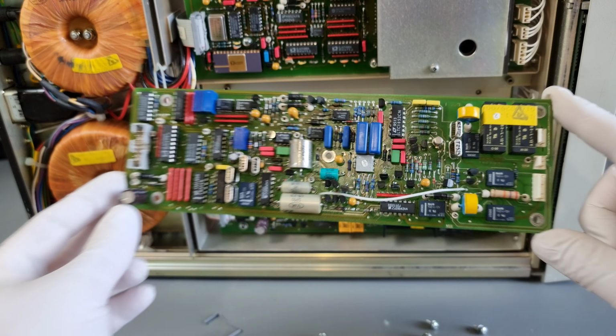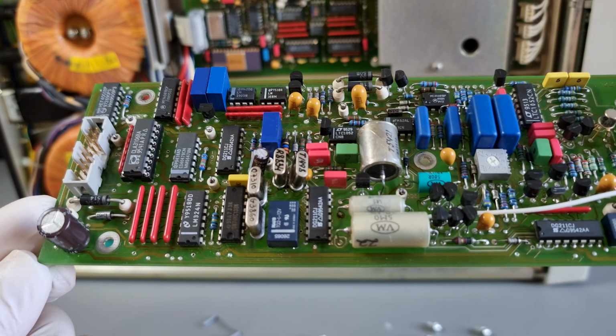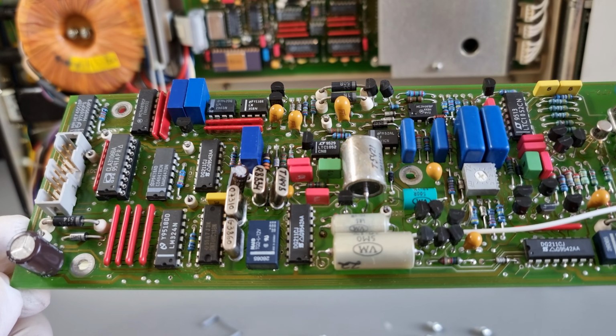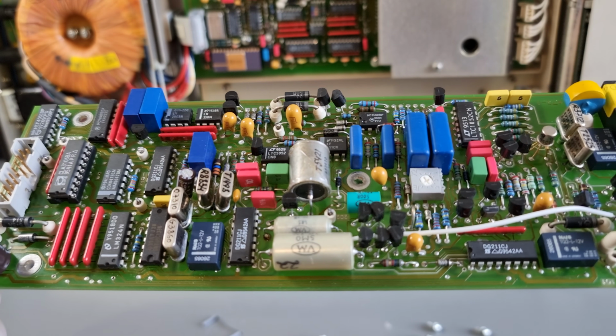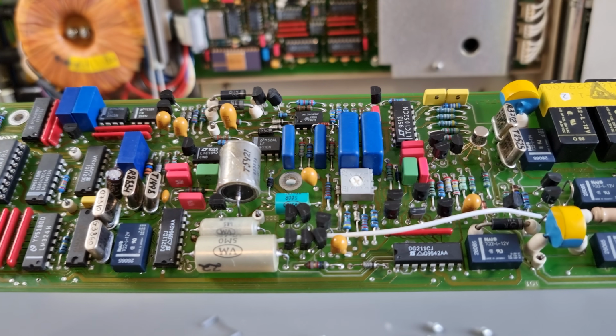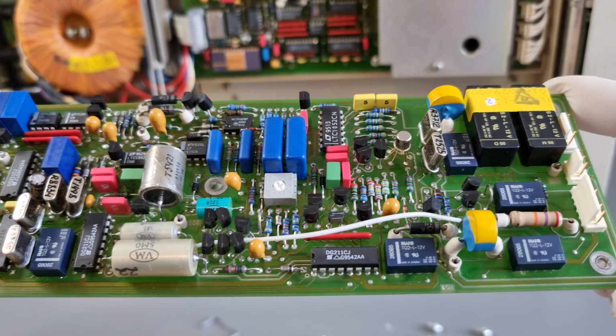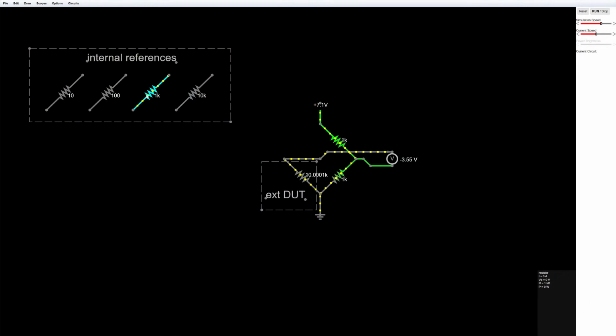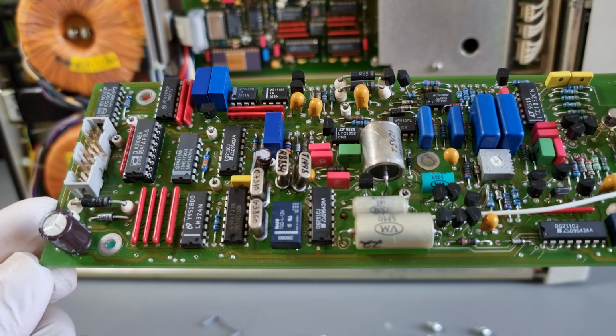Next up is the Ohms measurement assembly. This bad boy is dense and complicated, surprisingly so. The 4950's preferred mode of operation, only accepting a handful of nice and round standard resistor values, I would have thought made it the perfect place to employ a resistance bridge measurement technique, where it could simply swap in one internal reference resistor per range and measure deviations of externally connected DUTs with its own built-in low-voltage preamp.